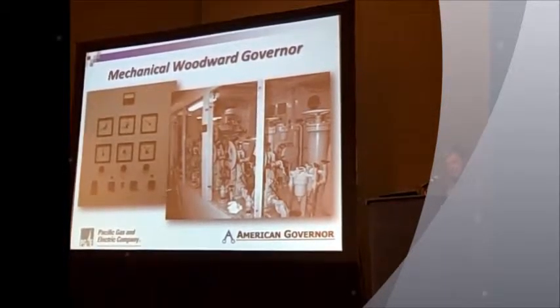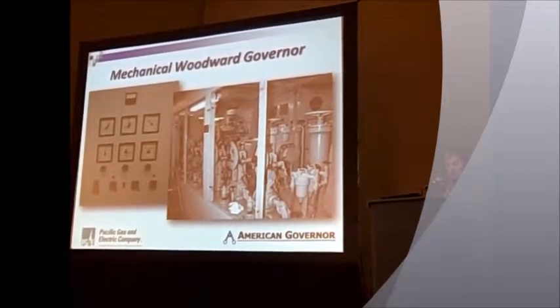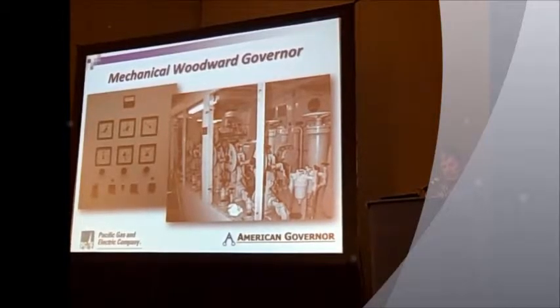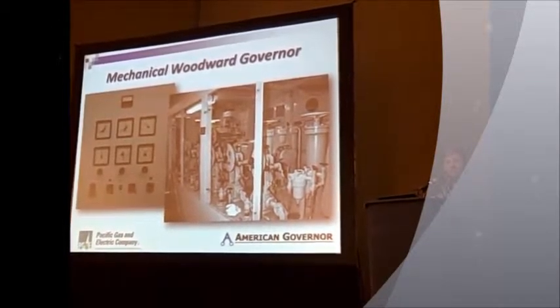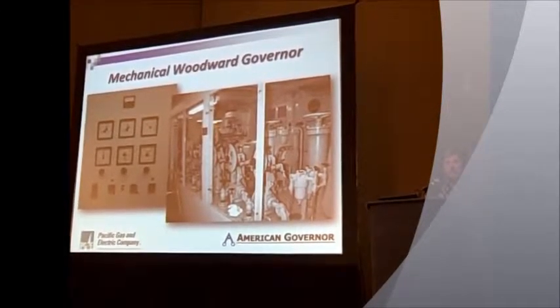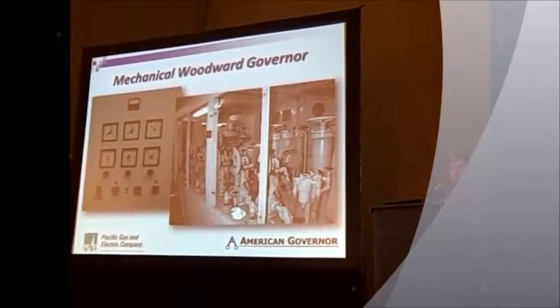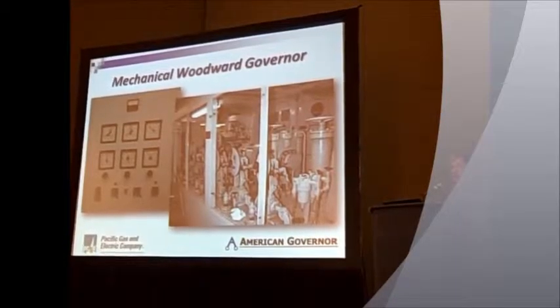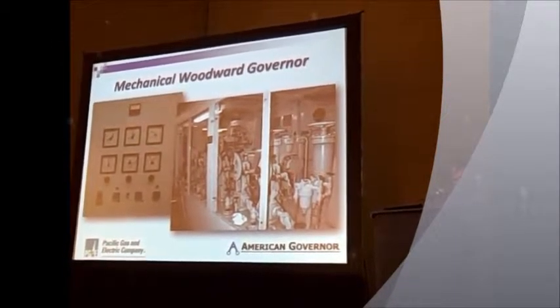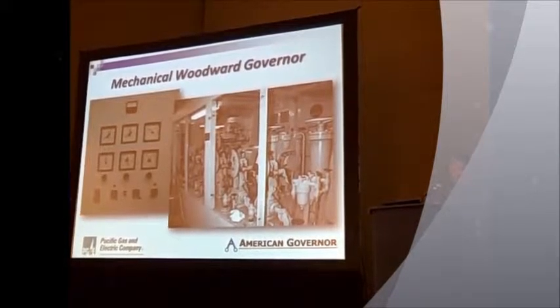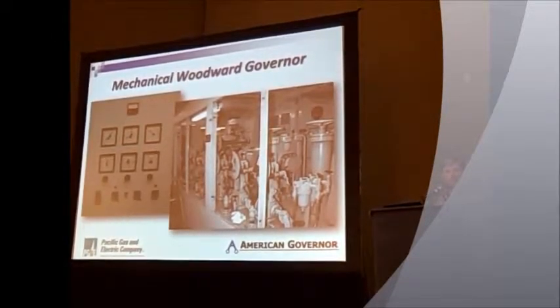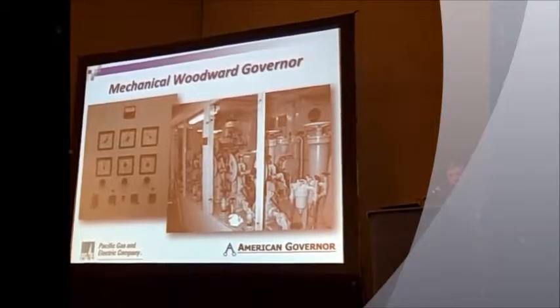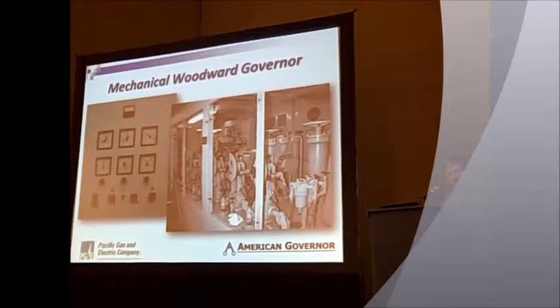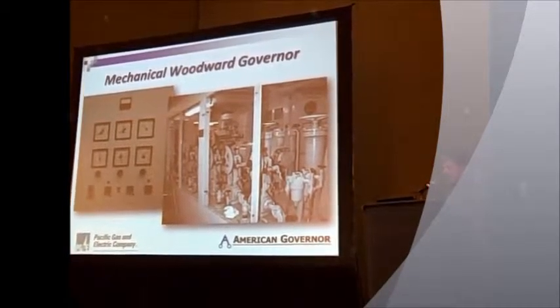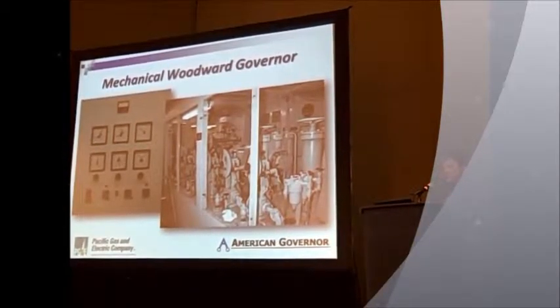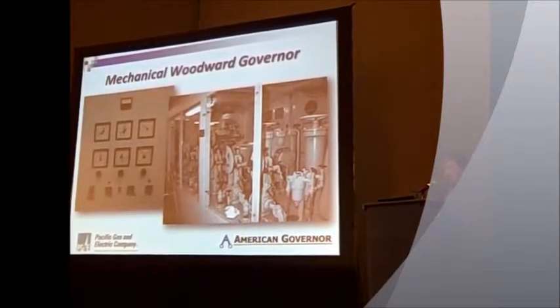Until recently, the speed control was managed with a 1960s Woodward governor, a mechanical governor. This governor utilized over 450 feet of steel cable for the needle restoring, needle feedback, almost a ton of counterweights and countless sheaves and pulleys. It kind of looked like an erector set that I built in 3rd grade. As with anything this age, we had normal wear and tear issues. It was difficult to keep this unit tuned. We had excessive hunting. It was difficult to parallel at times. And of course, with all these hydraulics, we had multiple oil leaks all the time. This cabinet was continually impacted by an oil film.